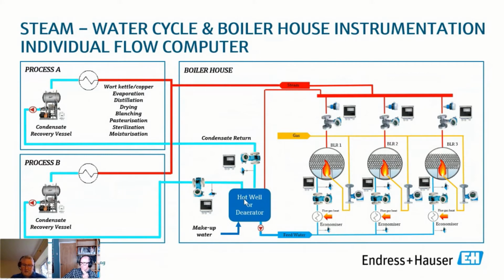So it's a simple cycle. These boilers have economisers, so the flue gases preheat the feed water, improving efficiency by a couple of percent. We're looking at temperatures across that economiser - these need to be a matched pair of temperature sensors. It's no use just taking two different temperature sensors and placing them there.